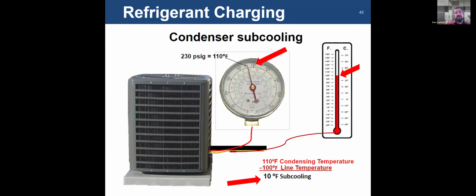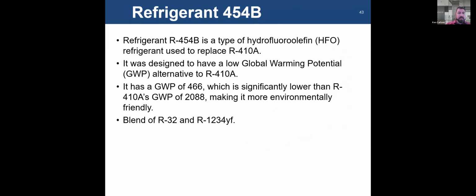Again, back to the gauge. It gives you a pressure. It gives you a saturation temperature. If you were at 230 psi, which equals a saturation temperature of 110 degrees, and you measured 100 degrees on your liquid line going out in cooling mode, you would have 10 degrees of subcooling. I don't think this is actually for 410A, so don't pay attention too much to those numbers, but the theory is essentially the same. So that's all I have for refrigerant charging, superheat, and subcooling.